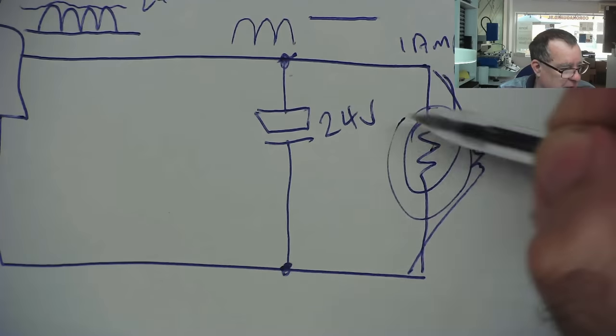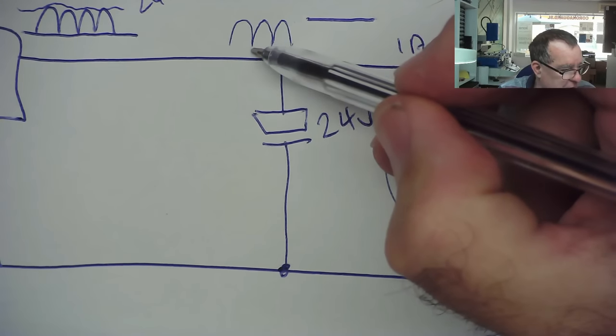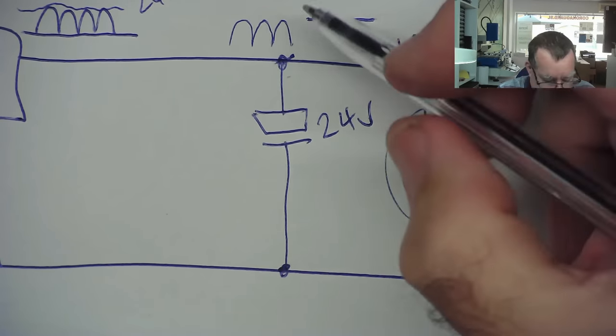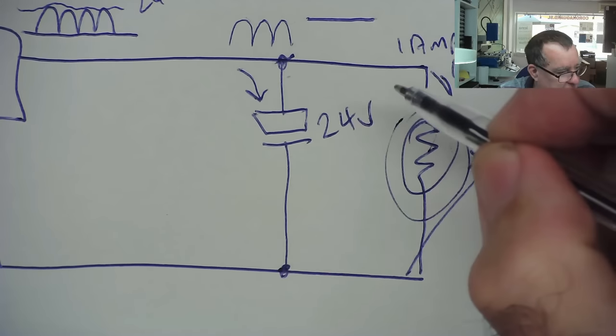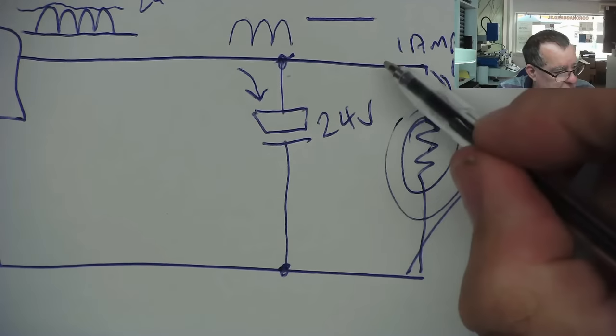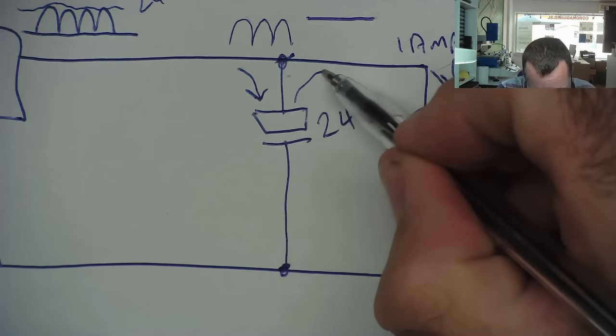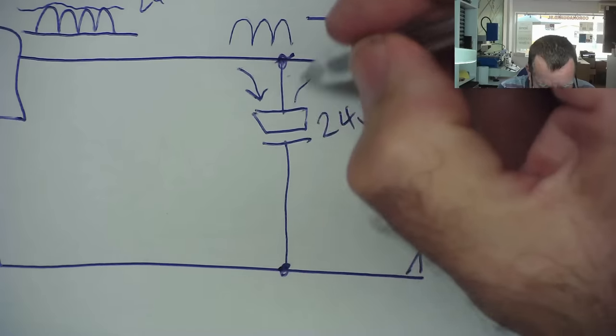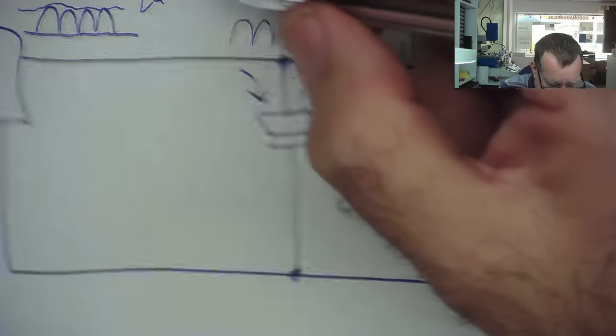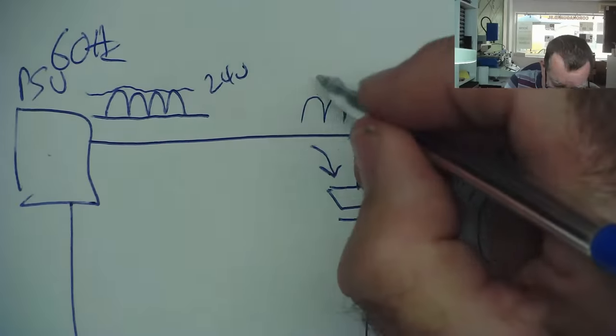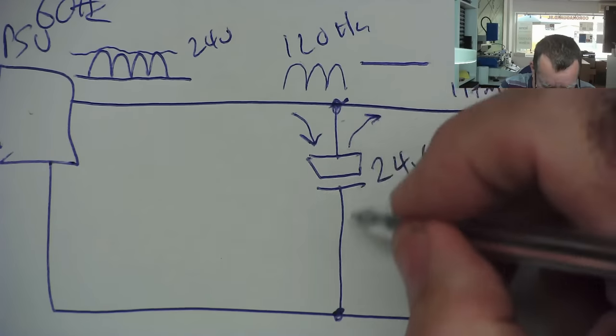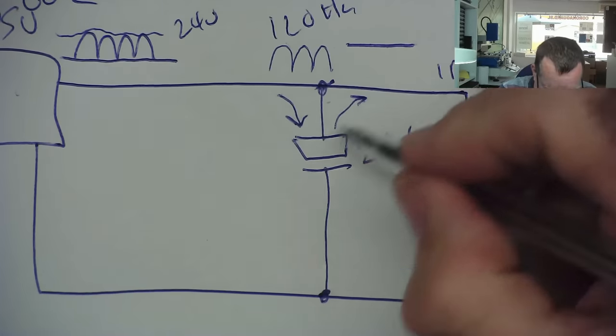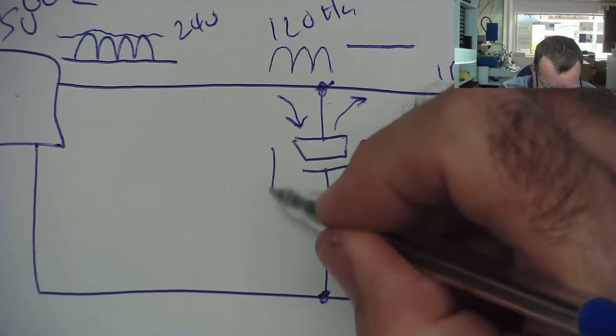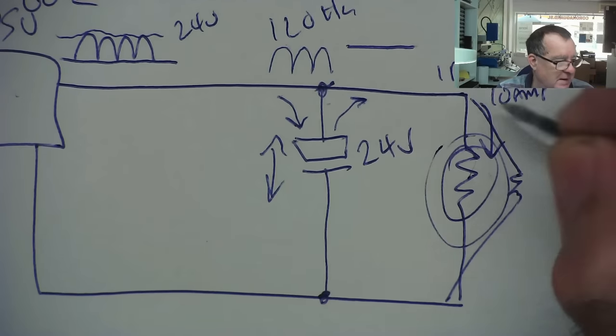What happens now is this capacitor tries to supply the voltage during the trough, when there's nothing coming in. On the first peak it charges up and current flows this way. As the voltage drops, because of the current being drawn, the capacitor has to supply current back out to try and maintain the voltage. So it's repeatedly charge, discharge, charge, discharge. Depending on the mains frequency, if it's 60 hertz, this will be 120 hertz, so 120 times a second it's trying to charge and discharge very rapidly. That causes what's called ripple current, a current flowing backwards and forwards as it tries to maintain the voltage.